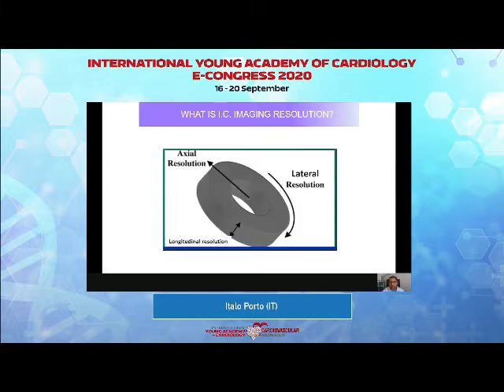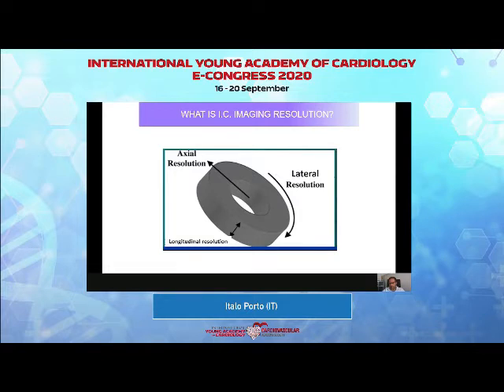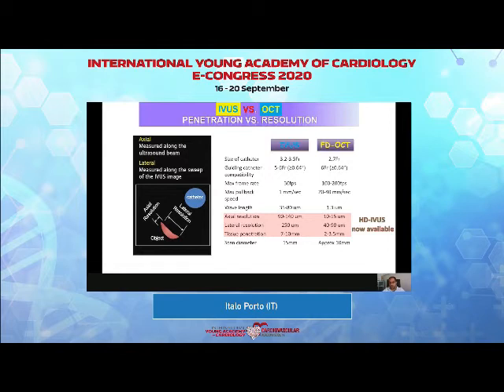What is resolution? We are talking about tomographic images — slices. We have three axes: longitudinal resolution, meaning how many slices we have per millimeter; axial resolution along the scan line; and lateral resolution between each scan line. For IVUS we are talking about hundreds of microns, while for OCT we are talking about tens of microns.